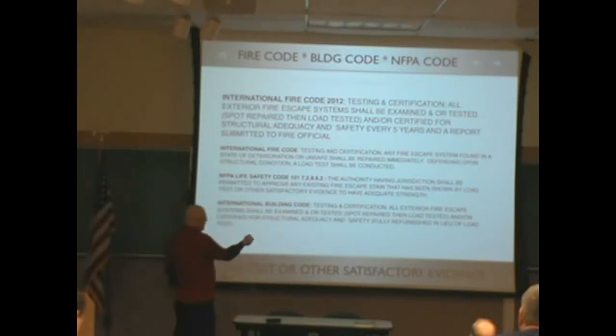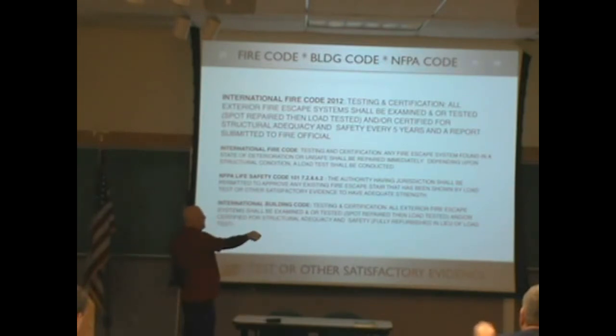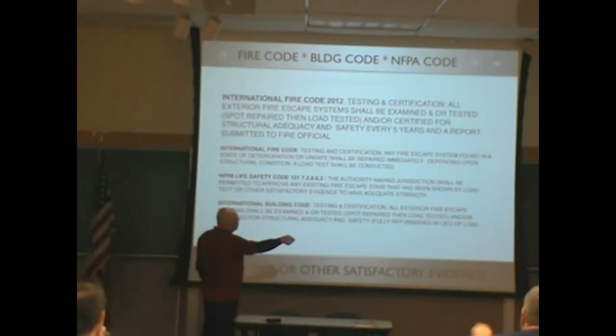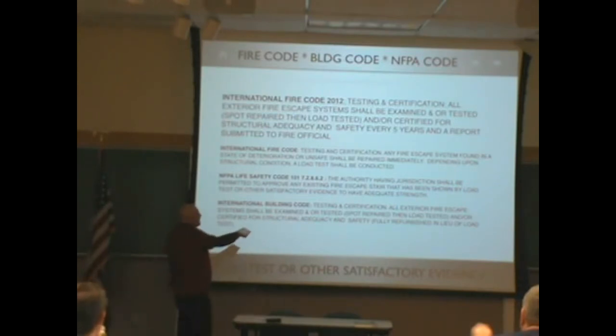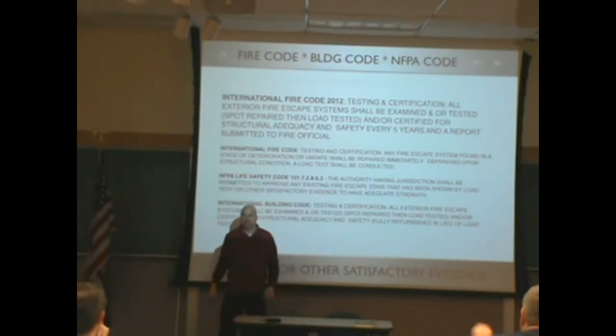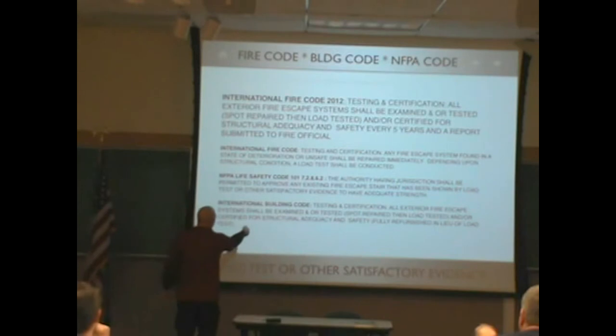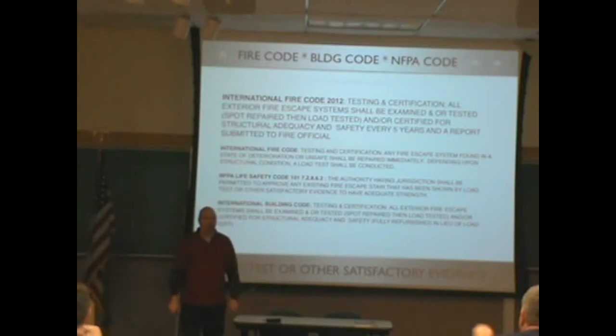The International Fire Code — same thing. In some of your fire codes it says anything in a state of deterioration will be repaired immediately, and depending upon structural condition, a load test shall be conducted. Let's get to your code — the NFPA. NFPA 7.2.8.6.2: 'The authority having jurisdiction shall be permitted to approve any existing fire escape stair that has been shown by load test or other satisfactory evidence to have adequate strength' — which means you control the opinion.